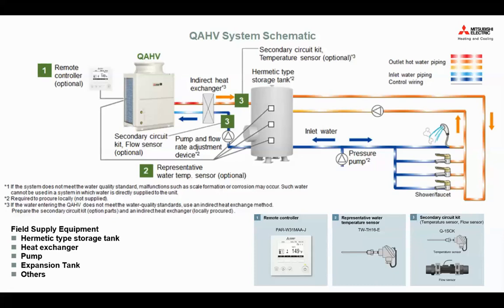So in here, just a general overview from Mitsubishi, the requirement or minimum is the QAHV, obviously the hot water heater, and also the remote controller and the sensor and the secondary circulation kit, the temperature sensor and flow sensor, just to make sure there's proper water flow around the unit, right? So you can set the leaving water temperature from our PAR-W31 controller, and you can also measure the cold and hot water from the other side, along with the flow to make sure there's no dry flow or dry run in the hydronic system.